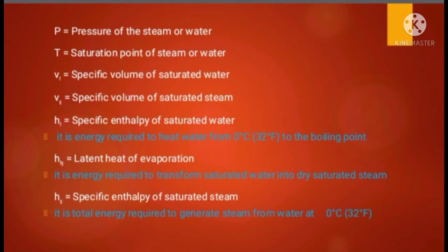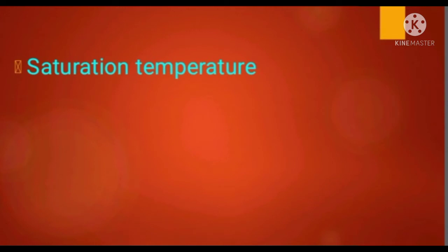Hfg equals the latent heat of evaporation. It is the energy required to transform saturated water into dry saturated steam. And Hg equals the specific enthalpy of saturated steam. It is the total energy required to generate steam from water at 0 degrees Celsius. Let's proceed to saturation temperature.